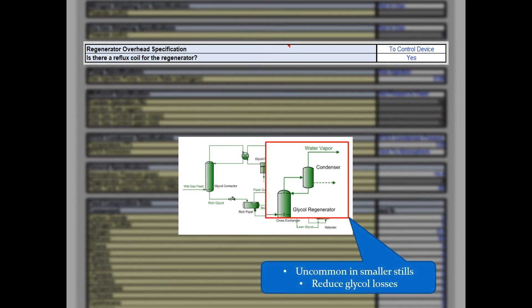As with the flash tank vapors, users need to define where glycol regenerator vapors are sent — either routed to a control device or vented to the atmosphere. Some glycol regenerators have a small reflux coil at the top of the column where cool rich glycol passes through to provide a little reflux, mainly leading to a reduction of triethylene glycol losses and emissions. Use the reflux coil regenerator dropdown to choose if one is present in your facility.